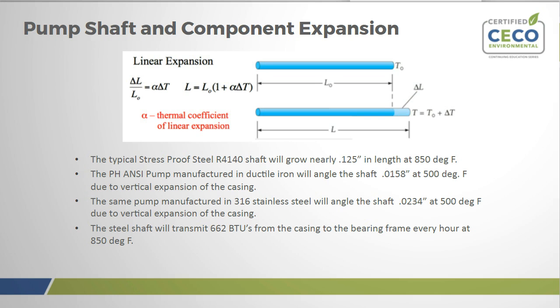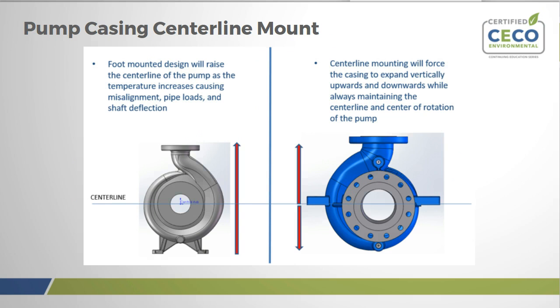And the different ways that we can negate these effects. For instance, for a pump casing, most ANSI pumps that you see out there, and most pumps are, have a foot mounting, at least for horizontal end suction pumps. The foot mounting, of course, as temperatures increase, the casing of the pump will expand, and all things expand from their base.